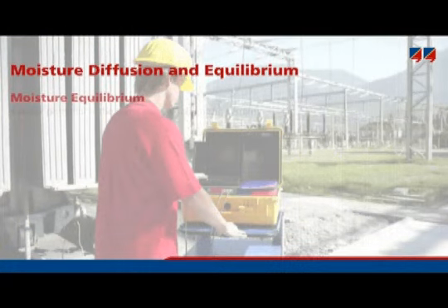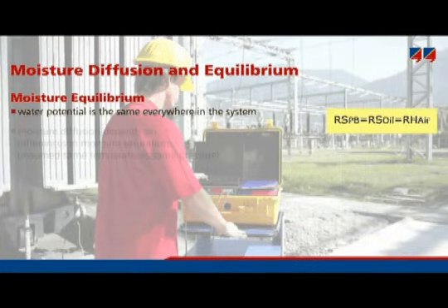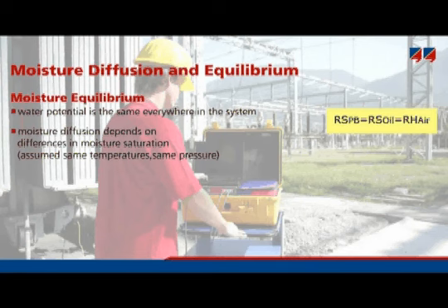After a while, the paper will have 40% as well. Equilibrium processes need time. This will be emphasized later. The same happens in a transformer. Under equilibrium conditions, there is the same relative saturation in oil as in cellulose.